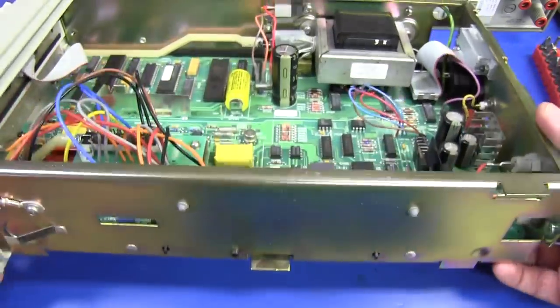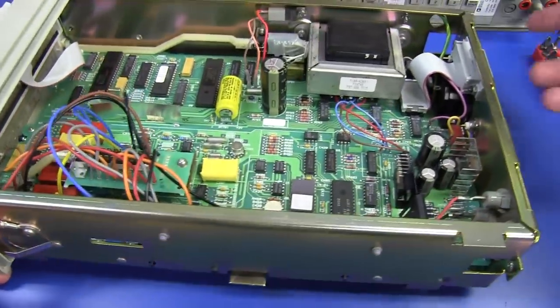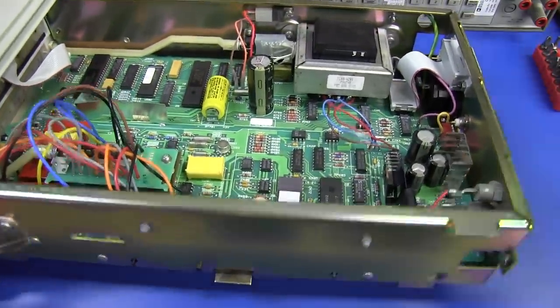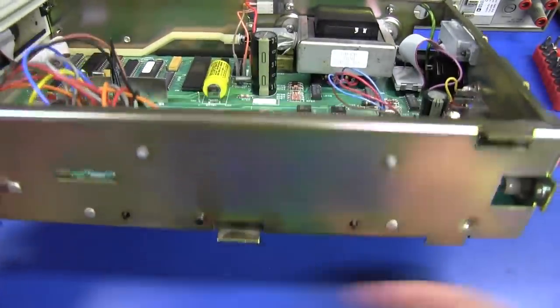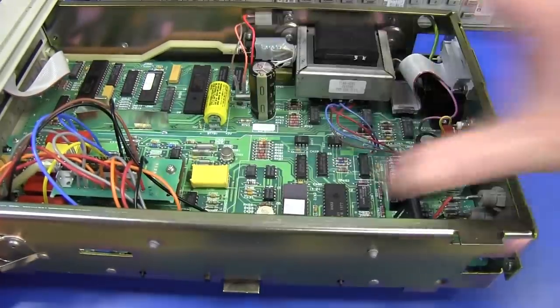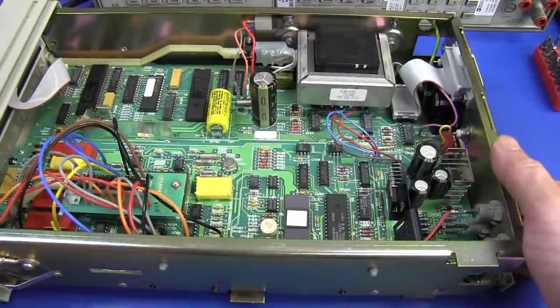This one is not auto line frequency sensing like the 3457A, which automatically when it powers up, detects the line frequency and takes care of it. This one you have to actually switch it between 50 or 60 hertz there. The case comes off this thing quite easily. There's just 2 screws at the back plus 1 on the bottom, and it just slides off.